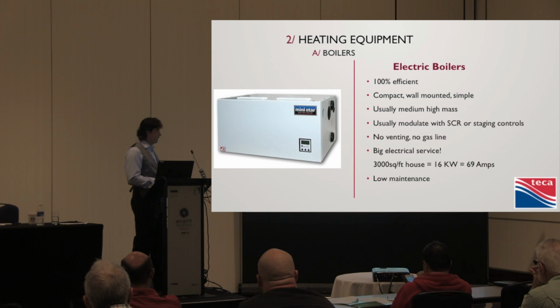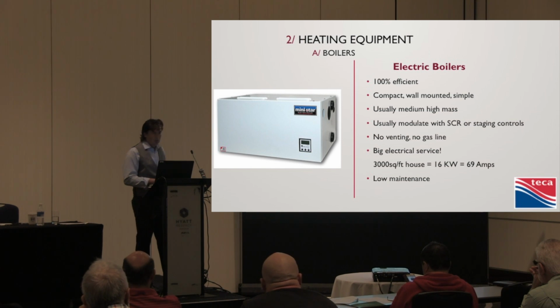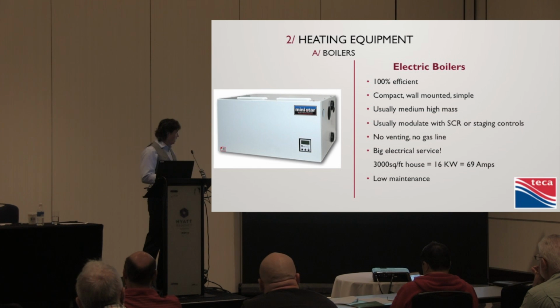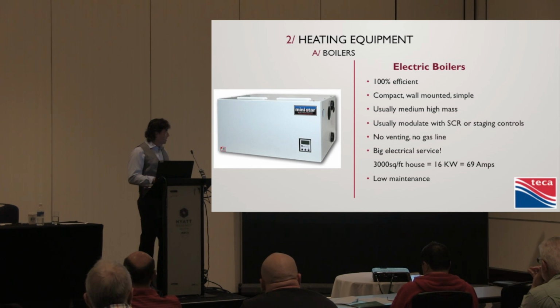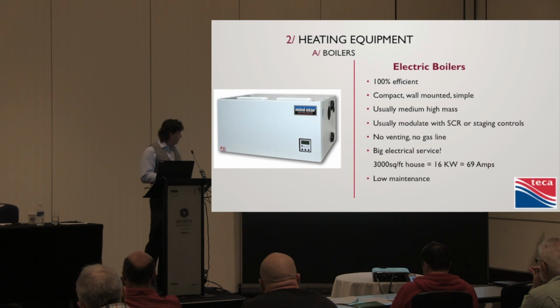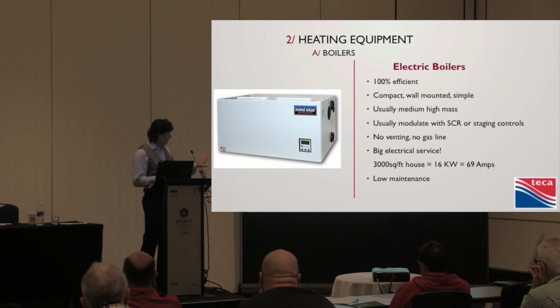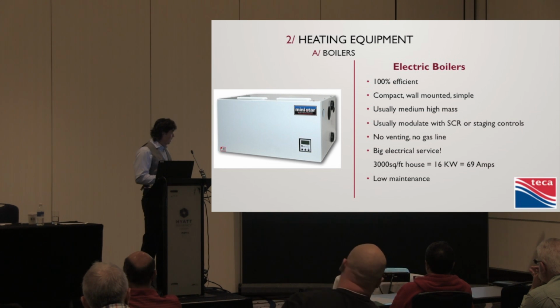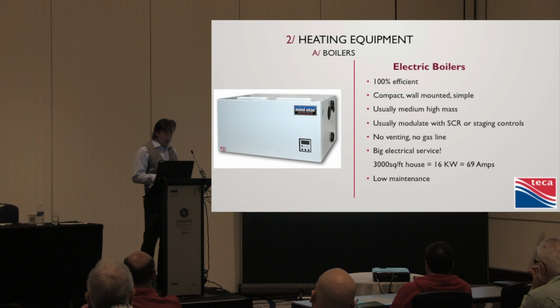You do have to, however, worry about an electrical service. So there's a time and a place for everything. 200 amps. So if we said a 3,000 square foot house, I'm just ballparking 18 BTUs a square foot here, you're going to wind up with 16 kilowatts, which is 69 amps of power devoted to your heating. If everybody's good with that, I'm good with that. I don't know what else you're doing with the house, but you got 200 amps. Maybe you got 400 amps, in which case you don't have a problem. But with 200 amps, you're going to want to look at this very closely. Let the electrician analyze that very closely before you get into buying one of these. Other than that, it's actually not a bad idea.